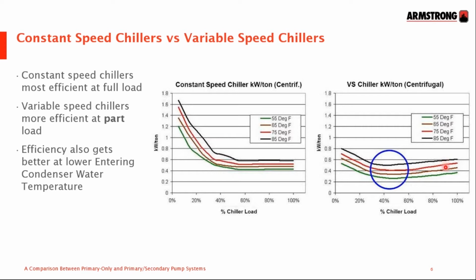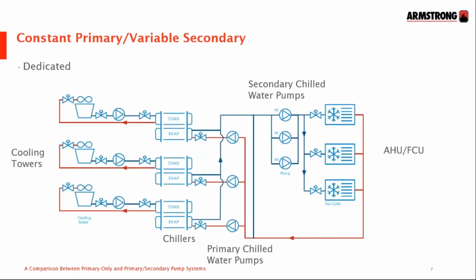But if you reduce that number, then the chiller becomes significantly more efficient. So we'll be looking at that as well and talking about that in the slides showing the control of chiller plant. So let's kick off with the constant primary variable secondary type circuit. It's a very common system.